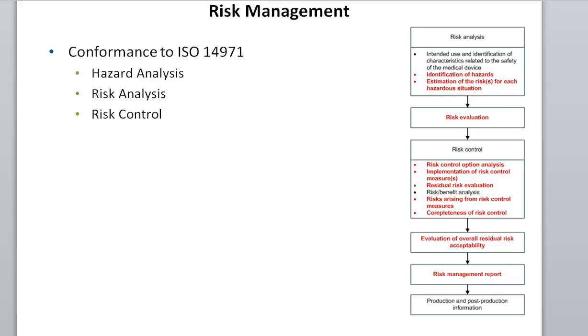So this is where we would identify all the sources of the hazard, what ways a user can overdose. One risk might be that if you gave the patient control to ramp up the amount of medicine being delivered and there's not enough feedback mechanisms to the user to indicate maybe they're over-medicating themselves. So the estimation of those risks are all about identifying the severity of that risk and the probability of occurrence.